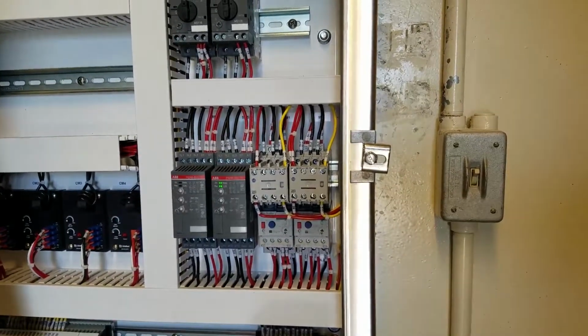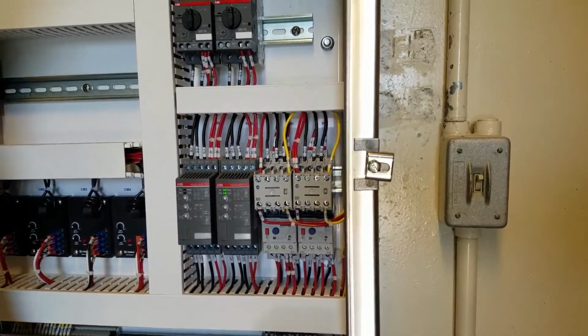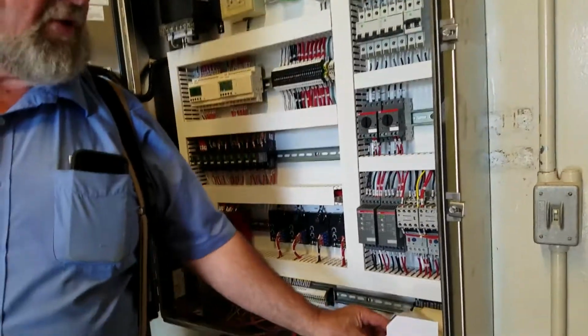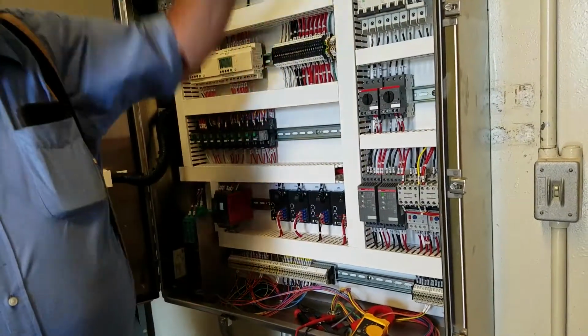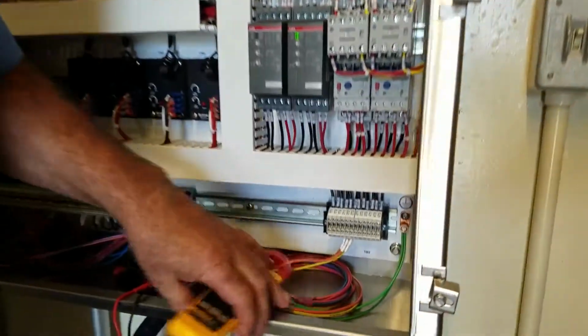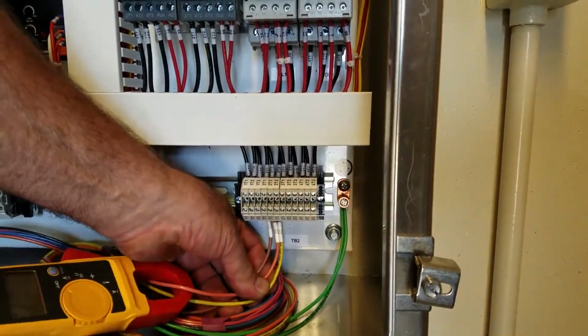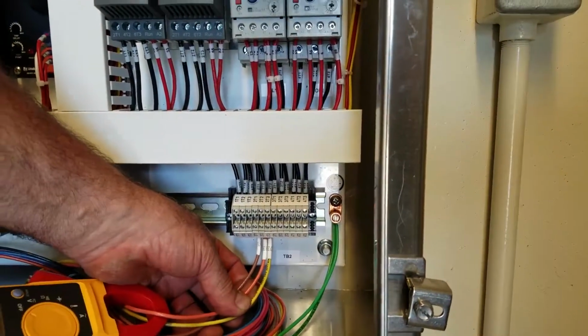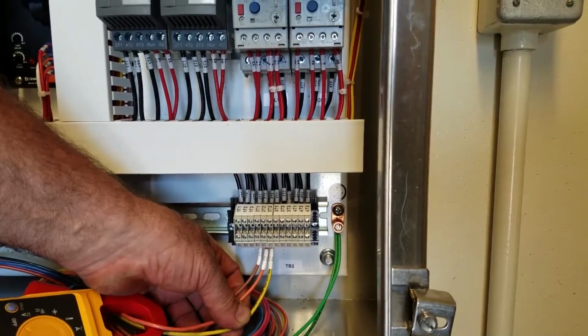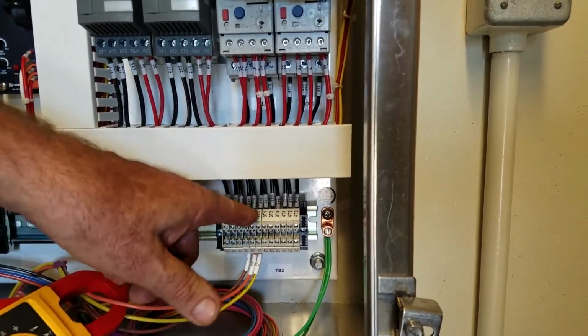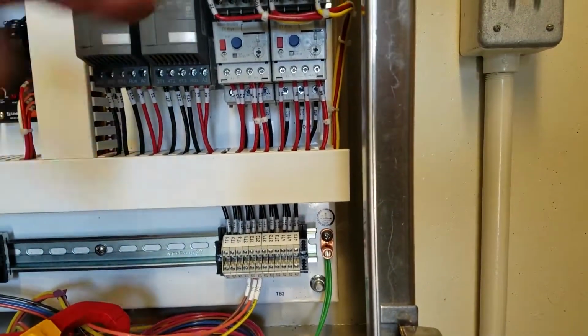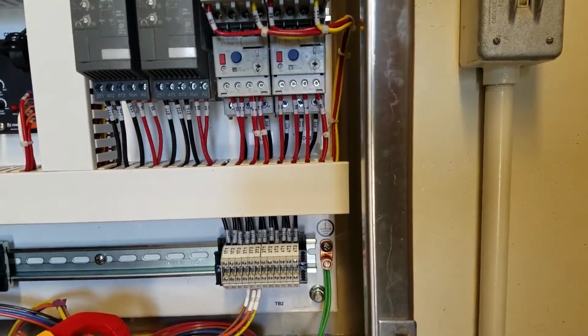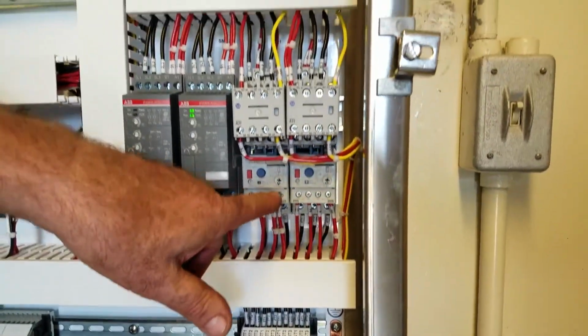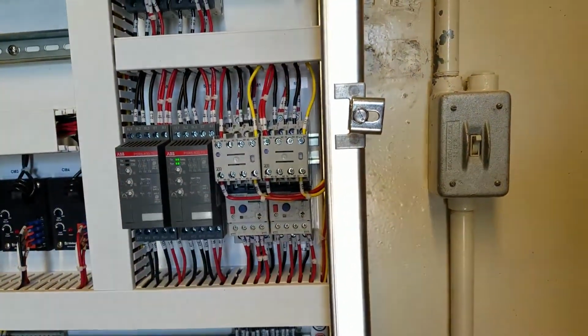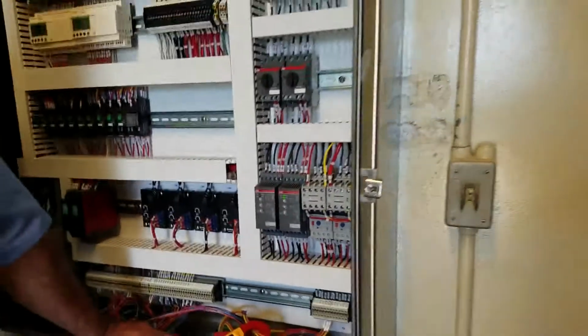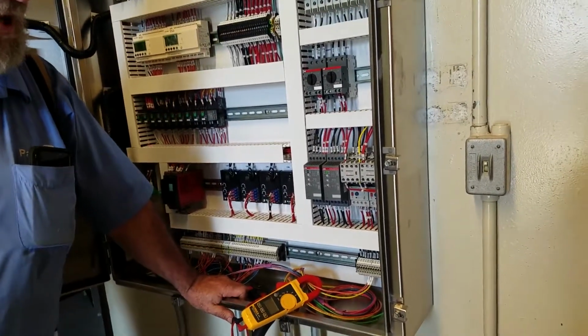If you ever have a problem with a motor and you want to avert any arguments from the motor manufacturer, you disconnect these wires from the terminal block and tag them so they go back in the right place if they don't have tags on them now. You get a megger tester and you megger test it from the panel with it disconnected. If you megger a soft start, you're going to cook it. Some of these overload relays may have delicate electronic equipment in there that may be damaged too, so it's always a good idea to disconnect from the terminal block.